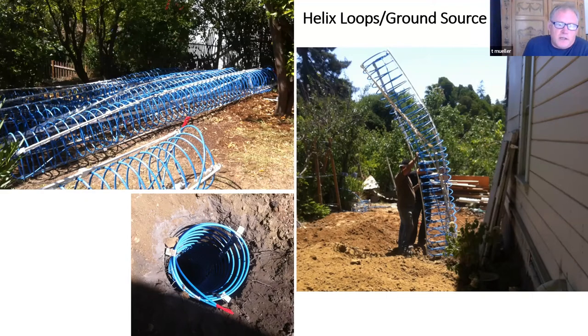I'll say this is an excessively designed system, unusual for our climate zone, but the water that goes out of that heat pump is at 34 degrees, and the water that comes back from the ground is at 54 degrees, almost without variation no matter what time of year it is. So it's a very, very stable place to exchange energy in the ground, which is why geothermal systems are so efficient.